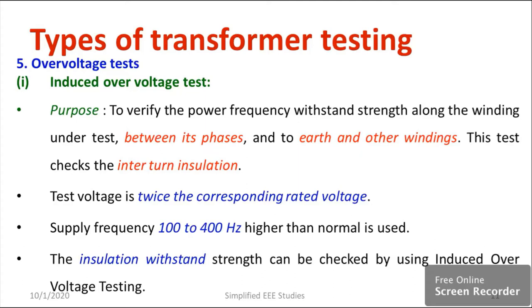Do remember these two conditions for induced overvoltage test: the voltage should be twice the rated value, and the frequency can be varied from 100 to 400 Hz. Under both conditions, no changes should happen in the insulation.